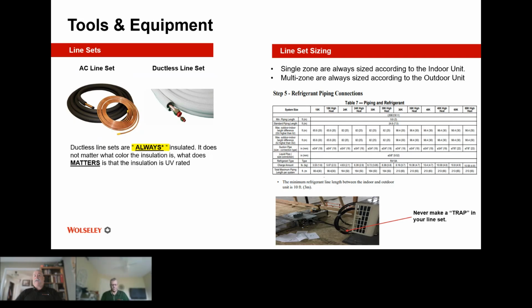And the reverse is for the multi-zone. We are always sizing our line sets according to the outdoor units. So depending upon the service port sizes, if they are a half-inch, 3/8, you use half-inch, 3/8 line sets all the way into all of your different head configurations, and then make the adjustments at the indoor head unit.